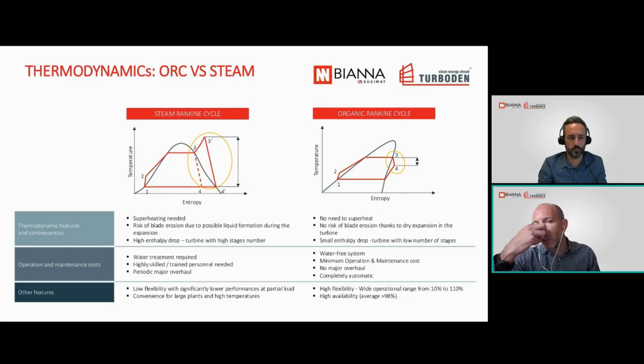So now, from a thermodynamic point of view, the biggest difference is that the steam needs to be superheated to work properly in a turbine, while that's not necessary for organic fluids. When organic vapor expands in the turbine, it always stays dry. There is no condensation, no liquid formation, and that's a big deal because there is no risk of blade erosion, which is something that can happen in steam turbines. We all know if pressure and temperature are not perfectly controlled, that's a risk.